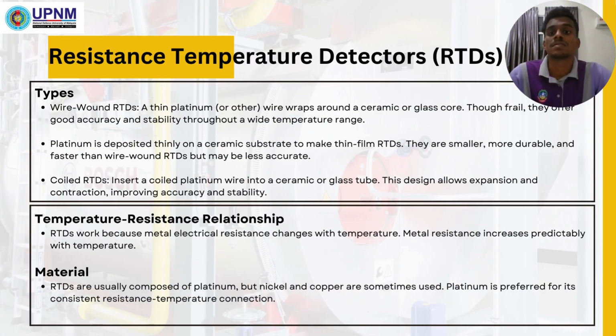Next up, let's look at the resistance temperature detectors transducer, also known as RTDs. There's three types of RTDs. The first one is wire wound RTDs. The second one is thin film RTDs. The third one is coiled RTDs. These RTDs are basically made with platinum, but nickel and copper are sometimes used.